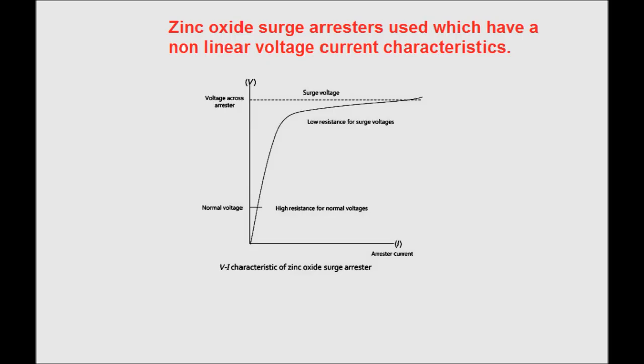Modern days, zinc oxide surge arresters are used, which have non-linear voltage-current characteristics as shown in this diagram. During normal voltage, it provides high resistance so that no problem occurs under normal operation. But during any transient overvoltage caused by lightning overvoltage or switching overvoltage, it provides low resistance or low impedance towards ground, thereby protecting the costly equipment from the surge.